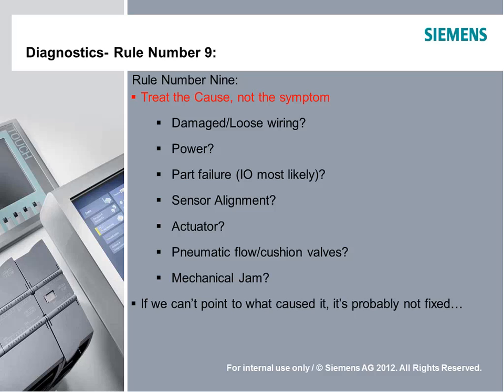Sensor alignment. I spent a good half a day on a machine one time where we were absolutely positive there was a software bug, because it was a new install. It had been running for about a week, but it kept having the same problem. It was a pusher arm, and it was sticking out and wouldn't come back. Apparently the guys on the floor would shake it around a little bit and it would come back again, and we couldn't figure out why.